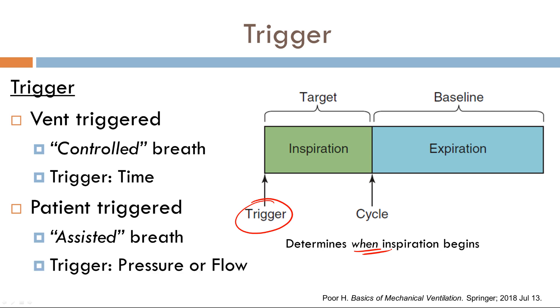Now let's contrast that with an assisted breath. In an assisted breath, the trigger variable is either pressure or flow. The patient triggers a breath themselves, which changes either the pressure or the flow in the circuitry, and that triggers the breath. It is up to you, the operator, to decide whether the trigger variable is pressure or flow. Conventionally, the majority of the time the trigger variable is flow.